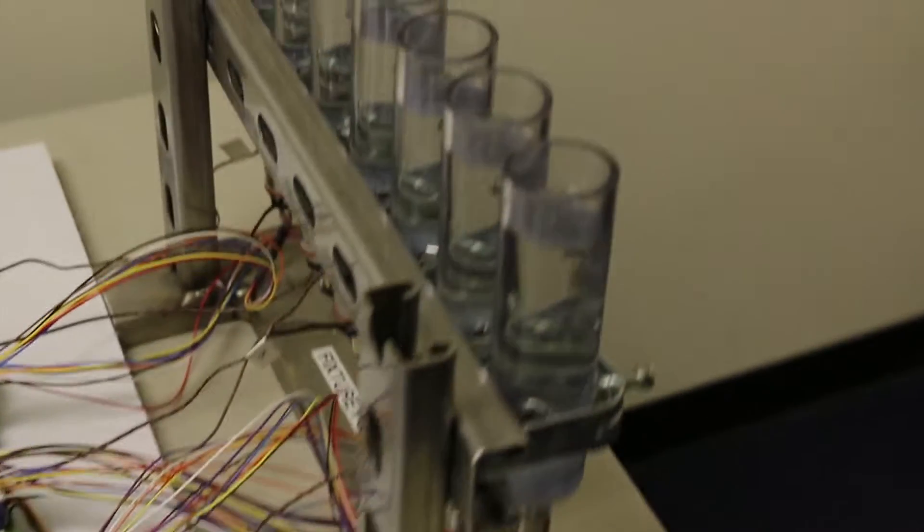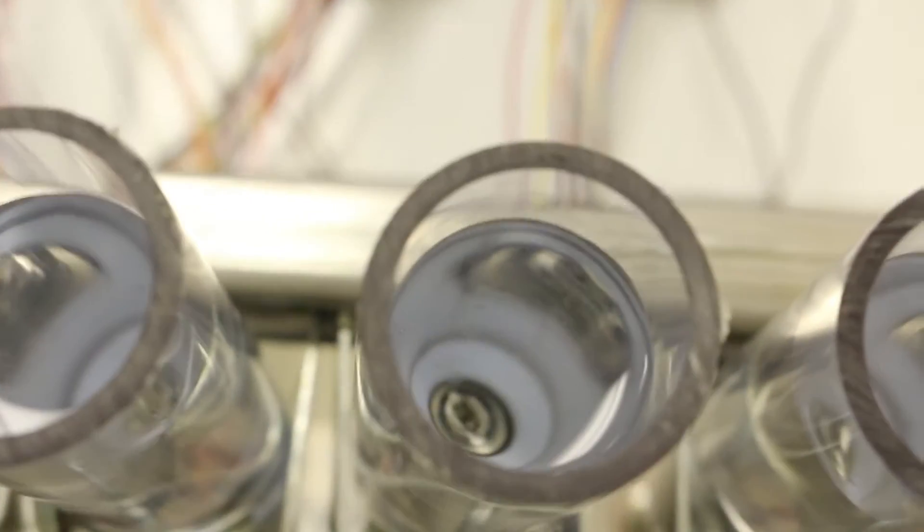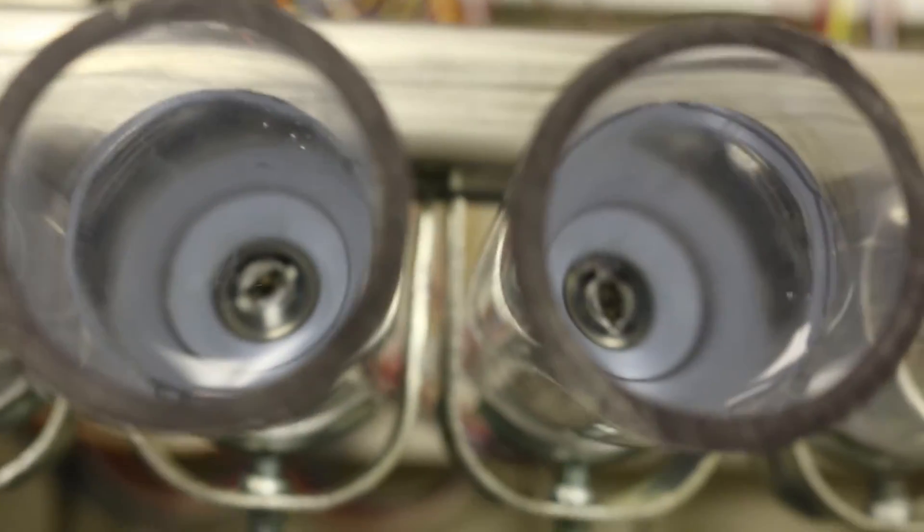After running on this station, the motors are then exposed to two cycles each of an autoclave and low pH detergent dishwasher. They are then placed back on test and this process is repeated until failure.